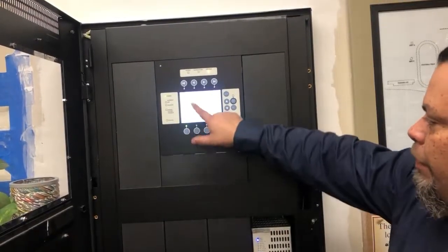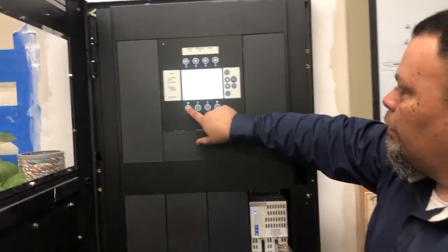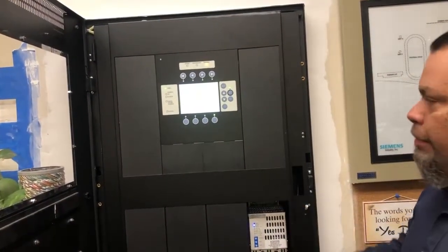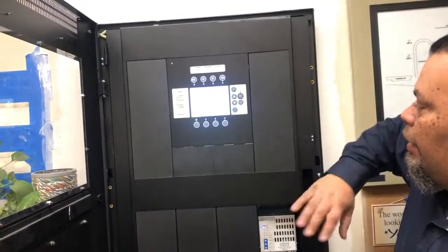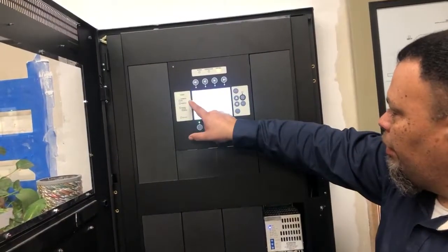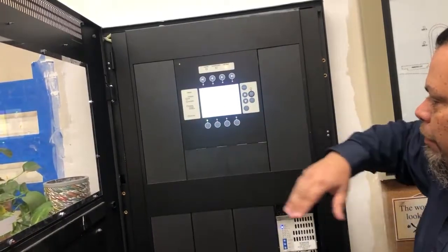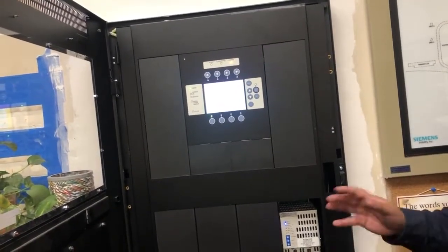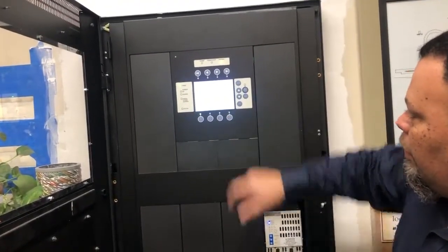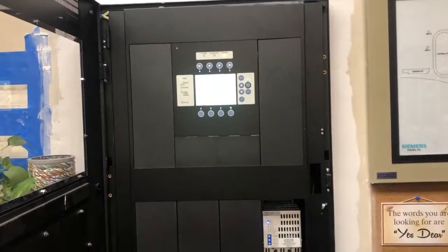That's going to give you a trouble every time you disable one of these things because it's telling you, hey, you're doing something that's not going to let the system work the way it's supposed to. So it's always going to give you a warning. It's not a bad thing. It's just a description that says the panel's not going to fully function at this time. So I hit the bypass horn strobes, execute. Bypass elevator controls, execute. Whatever you need to disable for whatever purpose is here in the function key. To re-enable them, you just press the enable horns and strobes, execute, and you're good. It's no longer a condition on the screen.